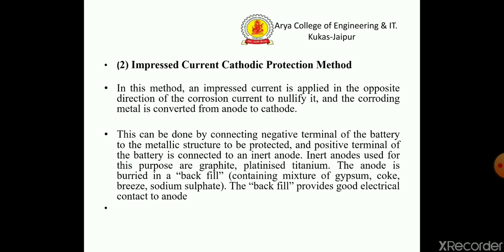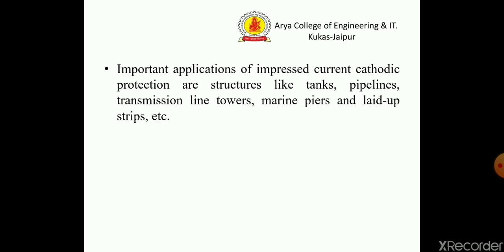The positive terminal of the battery is connected to an inert anode. Inert anodes used for this purpose are graphite and platinized titanium. The anode is buried in a backfill, which provides good electrical contact to the anode. Important applications of impressed current cathodic protection are structures like tanks, pipelines, transmission line towers, marine piers, and laid-up ships.